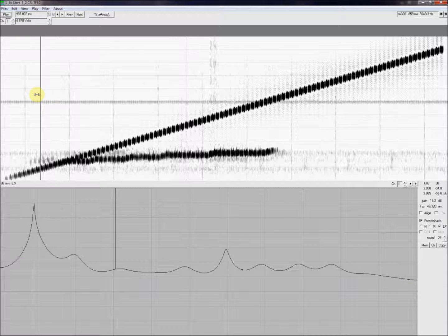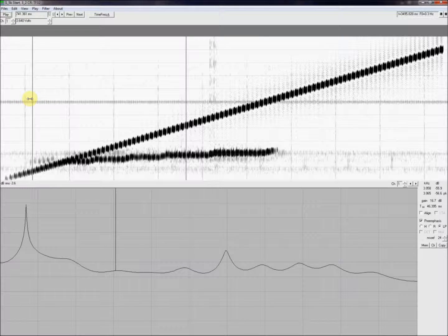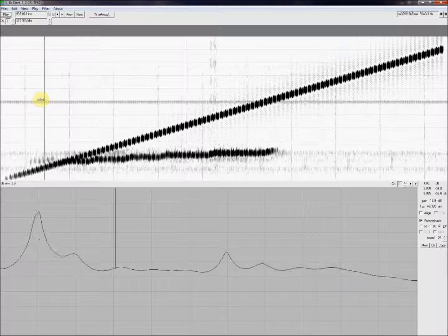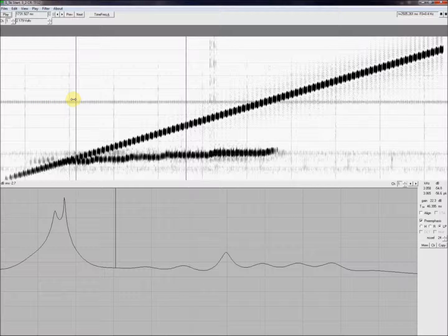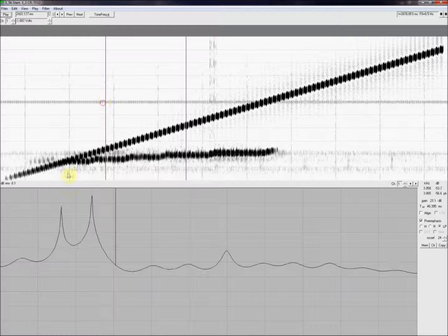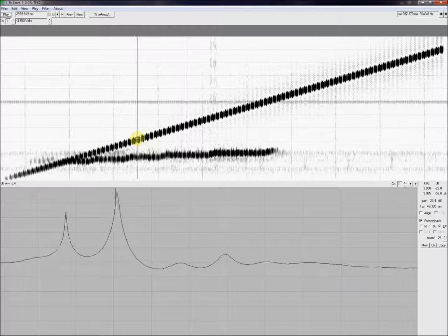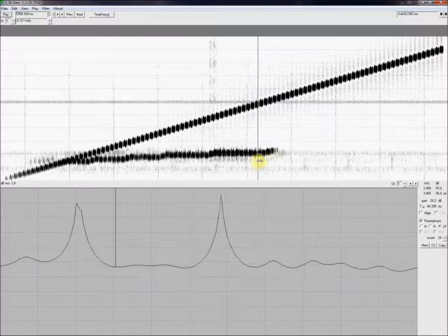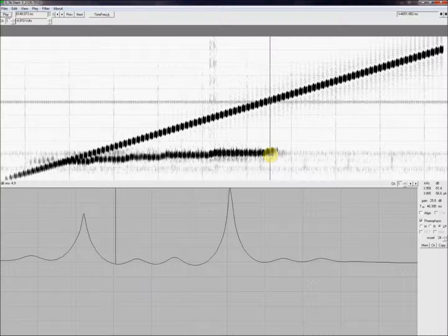In the low frequencies, there's just a single peak indicating that no lowering is taking place. Then around 1500 Hz, we see two distinct peaks. The higher peak corresponds to the input, and the lower peak corresponds to the output. We see that frequency lowering continues until we get to an input frequency of around 6100 Hz, at which point the information is lowered to around 2100 Hz.